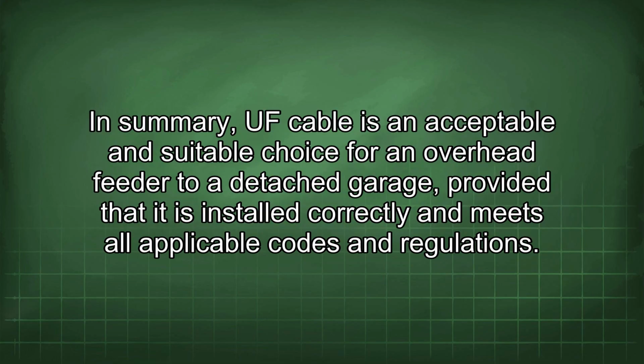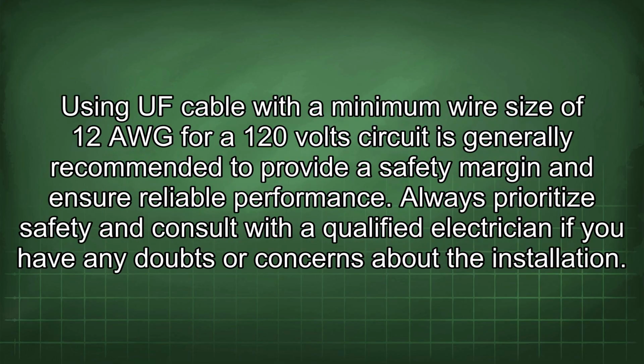In summary, UF cable is an acceptable and suitable choice for an overhead feeder to a detached garage, provided that it is installed correctly and meets all applicable codes and regulations. Using UF cable with a minimum wire size of 12 AWG for a 120-volt circuit is generally recommended to provide a safety margin and ensure reliable performance.